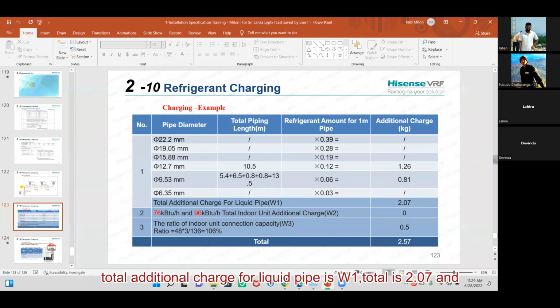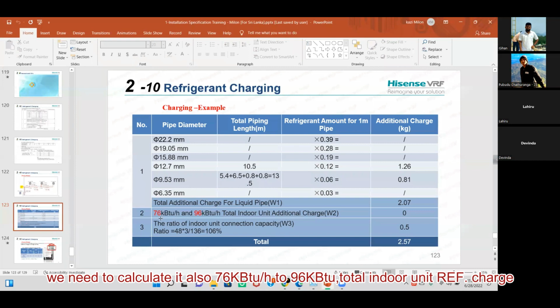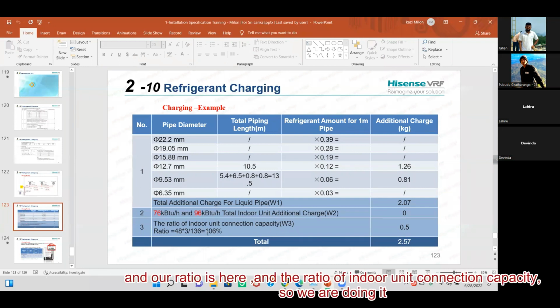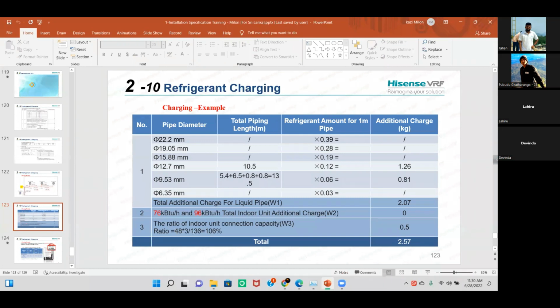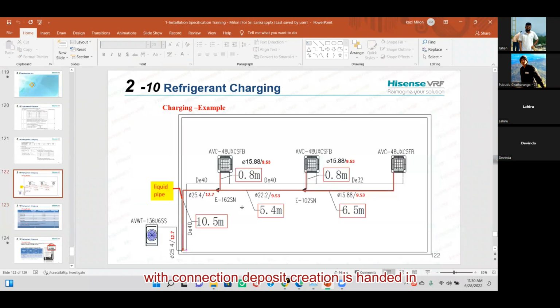Total additional charge for the liquid pipe, it's W1, its total is 2.07, and we need to calculate it also, 76 kBtu/h to 96 kBtu/h total indoor unit additional charge. And our ratio is here, the ratio of indoor unit connection capacity. Our indoor unit connection capacity ratio is 106%.